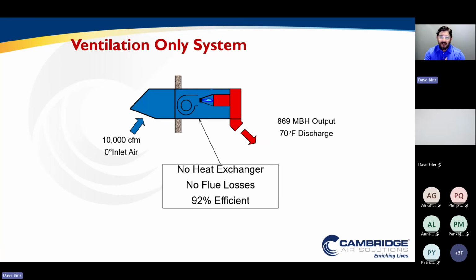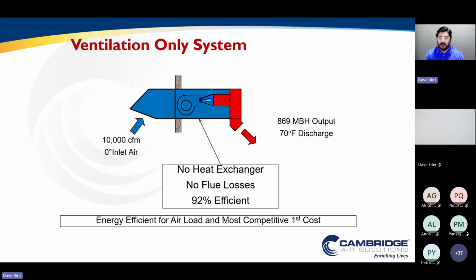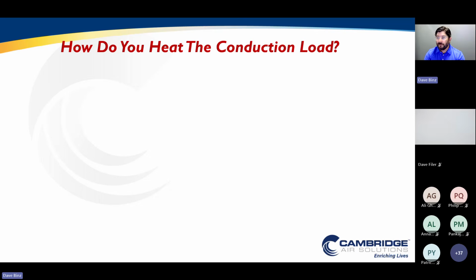So when I'm talking about energy efficiency, whether it's warehousing, industrial, or manufacturing, let's solve the ventilation problem first. If we take a warehouse, say a 150,000 square foot facility with lower outdoor air requirements, they may only need around 10,000 CFM to meet their ventilation requirements. That's not a lot of ventilation in a big open space. To heat that and provide ventilation energy efficiently, I'm going to use a direct fired system, again with no heat exchanger and no flue losses. There's your makeup air system.